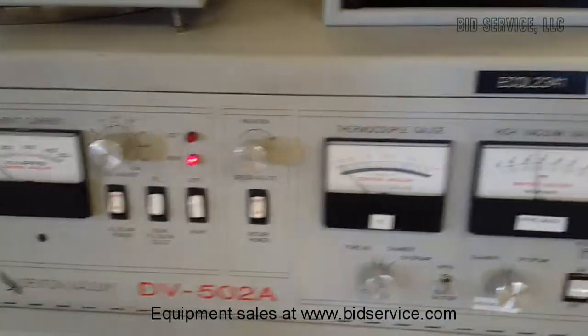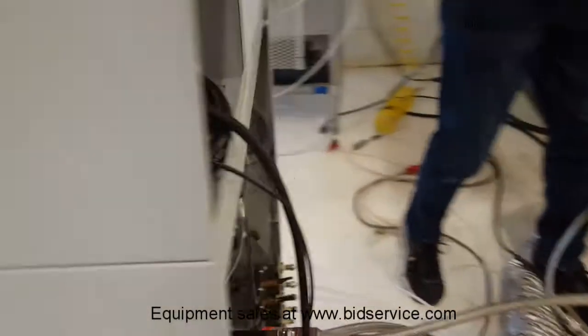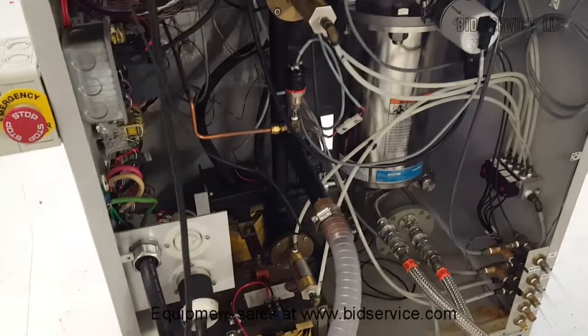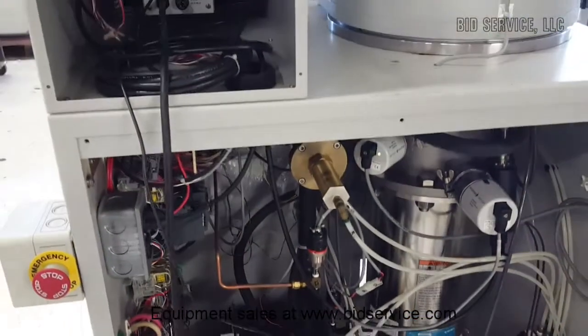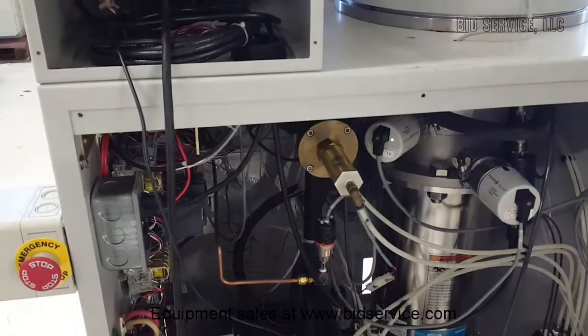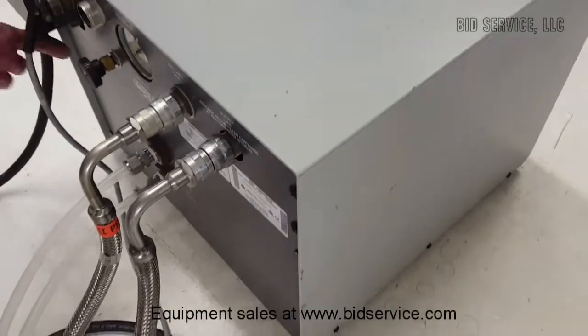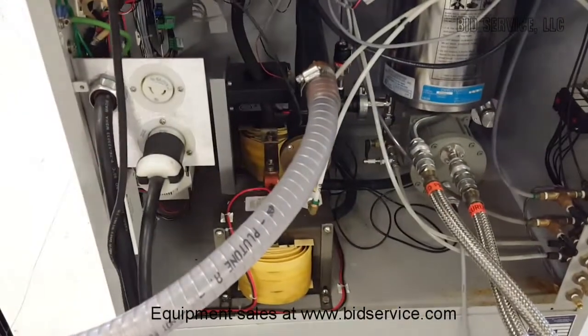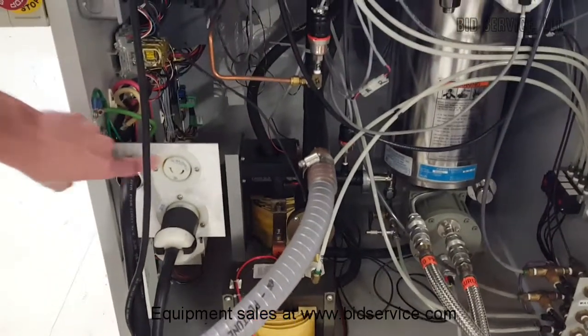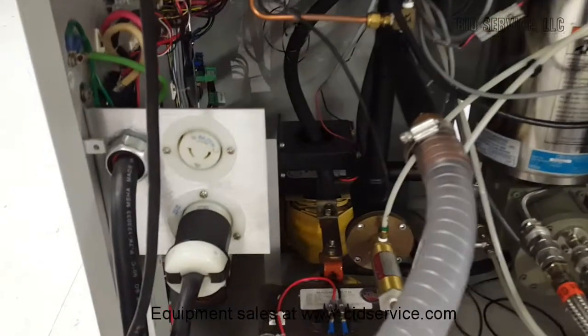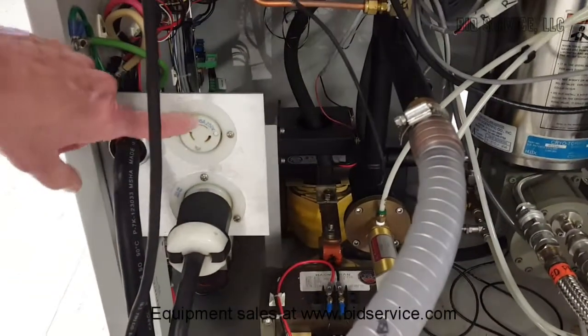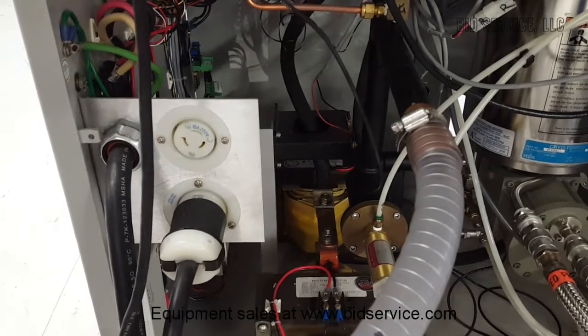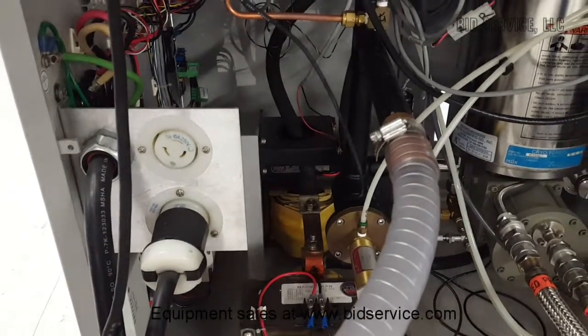Just going around the back here, I want to explain a few of the utilities. Over here we're using a chiller, so you're going to need chilled water for your compressor. This does not come with the system. This is our house unit, so you'll need to provide a chilling for the compressor over here. And the power for the compressor is run to the back of the unit here. You'll receive that plug. And just to note, the vacuum pump that we have right now is a house unit. We have the 250 volt single phase 15 amp pump being rebuilt right now, so we'll provide that before it's shipped. We'll get that ready for it.